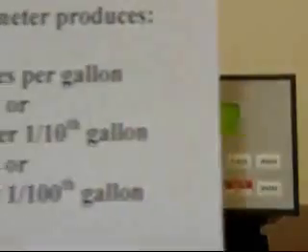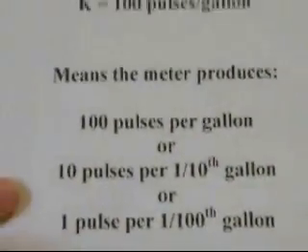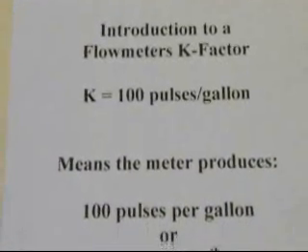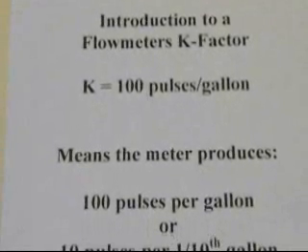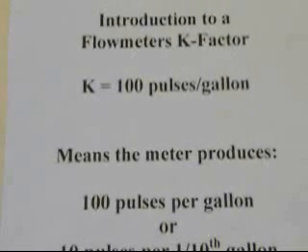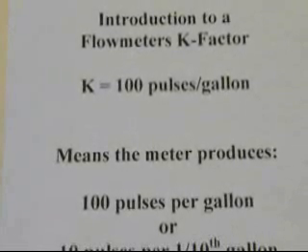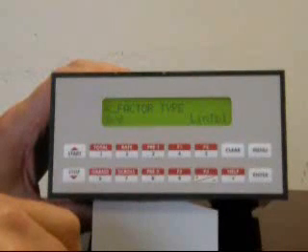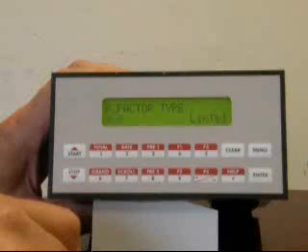There is now a selection for the K factor type that's going to be used. The K factor of a flow meter is usually provided in documentation by the company. This will normally be on a sheet of paper, may be stamped on the meter, or may be on a removable tag. Let's pretend in this application that we want to use a meter that has a published K factor of 100 pulses per gallon. If a meter manufacturer gives only a single value for the average K factor, sometimes called the mean K factor, you would be using the selection called average as to the type. If the meter is non-linear, you may wish to use the linearization table, which will require you to enter in additional point pairs of frequency and K factor. In this application, we're going to use the average K factor.